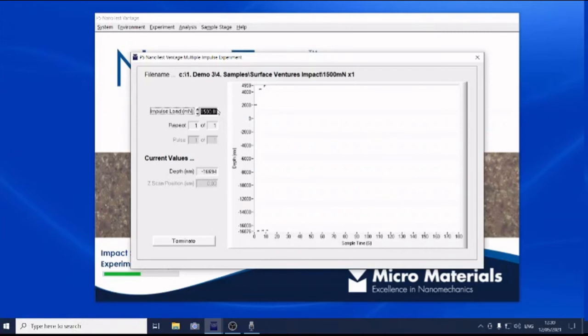there it is. Okay, and as you can see, with each subsequent impact, the probe is getting slightly deeper into the sample surface. So we're about 5.2 microns deep now. So 2 seconds in contact, 2 seconds out of contact. Okay, so depth continues to increase. Normally, a very, very abrupt failure would appear as a large change in depth between one impact event and the next. So depending on how sudden the failure is, the scale of the difference in terms of depth between one impact event and the next will change.